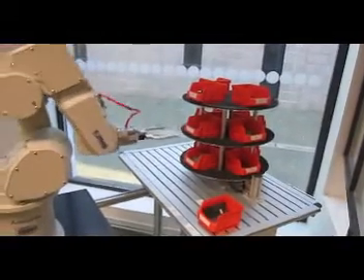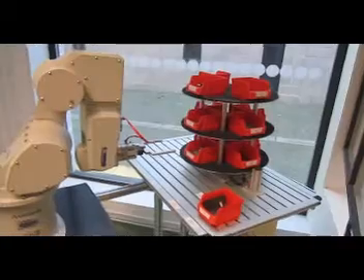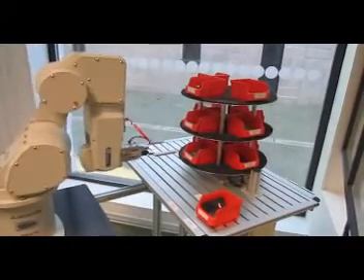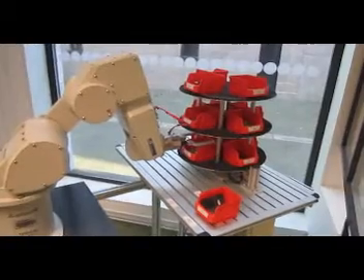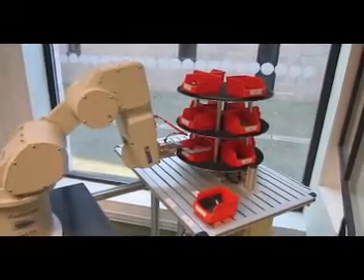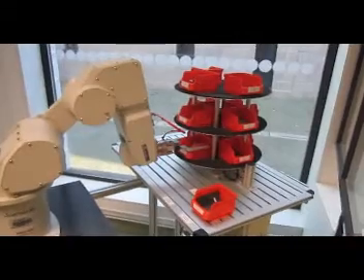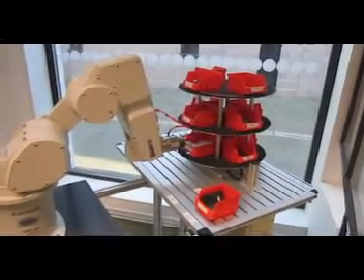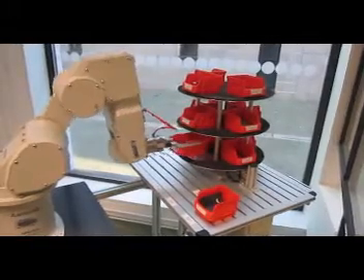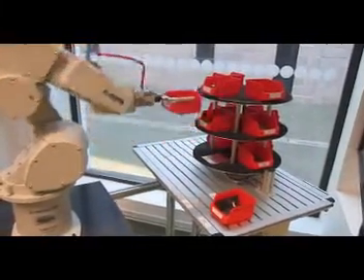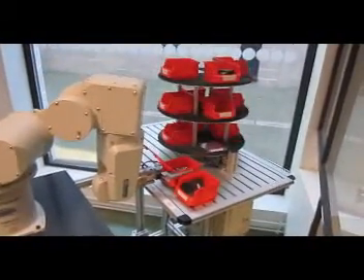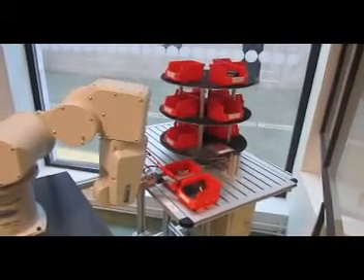Now it will go to the next position. It will go in above the bin, it will drop down over the bin, nice and slow to its position to avoid crashes. It will then close the hand, raise the bin, extract it. Now at this point the robotic arm has sent a signal to the PLC and the carousel to indicate that it is clear from the carousel and that the carousel is free to turn.